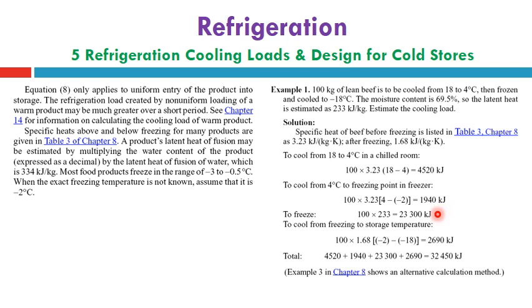and get finally the latent heat during the freezing process. And finally, to cool from freezing to storage temperature, the same 100 kilogram multiplied by the Cp, which we get from table 3 chapter 8, multiplied by the temperature difference of freezing temperature -2 minus -18, the final temperature at which this lean beef is to be kept. So we can get this amount finally as Q4 to get the total load of this product. We can have the sum of these four terms we have estimated in the above lines. So the final amount can be considered as 32,450 kilojoule. Example 3 in chapter 8 also shows an alternative calculation method.